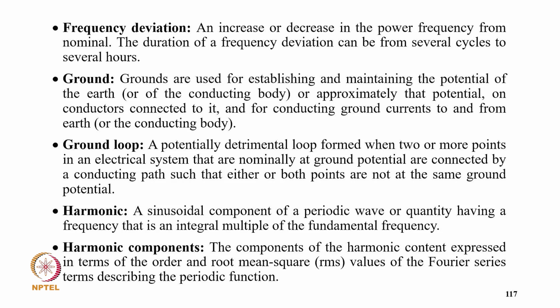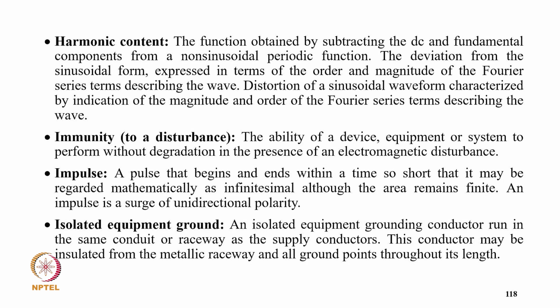Ground loop, a potentially detrimental loop formed when two or more points in an electrical system that are nominally at ground potential are connected by a conducting path such that either or both points are not at the same ground potential. Harmonic, a sinusoidal component of a periodic wave or quantity having a frequency that is an integer multiple of the fundamental frequency. Harmonic component, a component of the harmonic content, expressed in terms of order and root mean square value of the Fourier series term describing the periodic function. Harmonic content, the function obtained by subtracting the DC and fundamental components from a non-sinusoidal function. Distortion, the deviation from the sinusoidal form, expressed in terms of the order and magnitude of the Fourier series terms describing the wave.